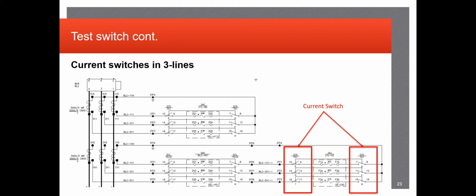Most of the time you can't do functional checks for continuity, because if it's energized, your meter becomes a short circuit and it can cause real problems. So most of the time, if you're going through an existing site, you have to do visual checks to verify everything's working.